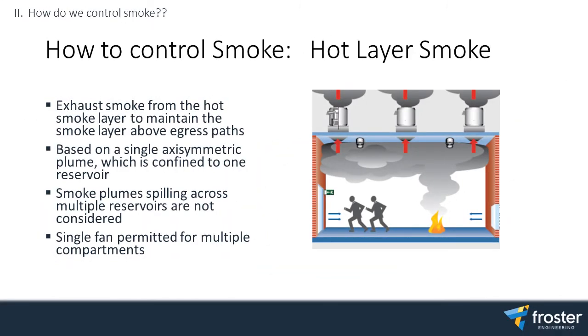This was recently introduced into 2015. Exhaust smoke from the hot smoke layer to maintain smoke above the egress paths. Now, honestly, I don't have any experience with this at this point. So again, the fire engineer would have to drive this solution. They pretty much tell us the exhaust quantity. We provide the fans to suit. Single fan permitted.